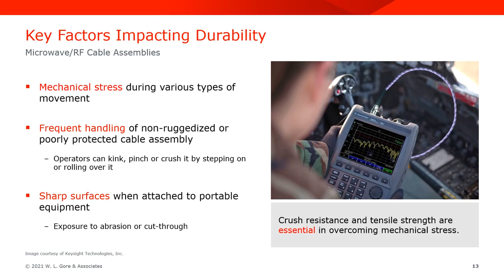An operator can kink, pinch, or crush a non-ruggedized or poorly protected cable assembly by stepping on it or rolling an office chair over it. Also, cable assemblies used with portable equipment can come into contact with sharp surfaces that could cut the cable assemblies or expose them to abrasion. So, crush resistance and tensile strength are essential in overcoming mechanical stress.